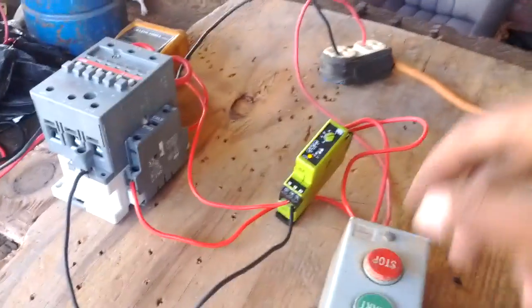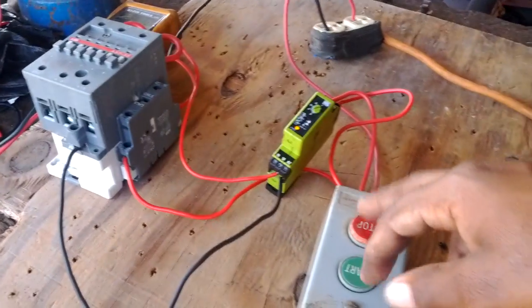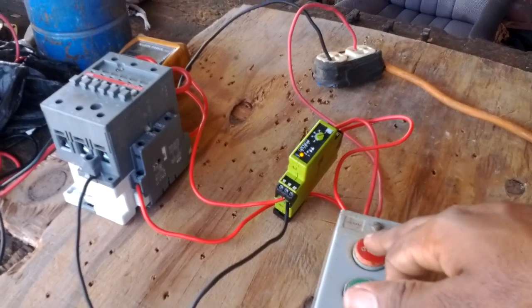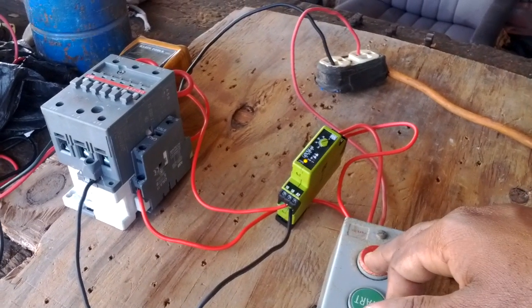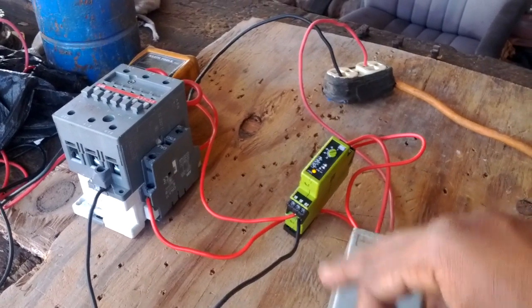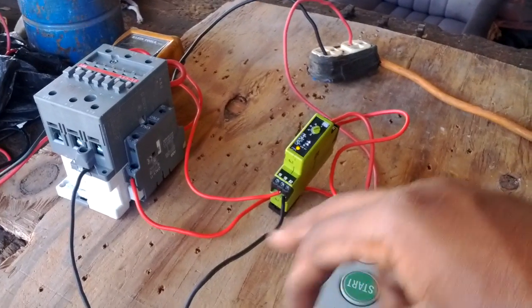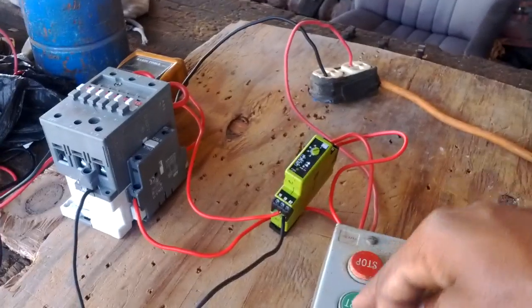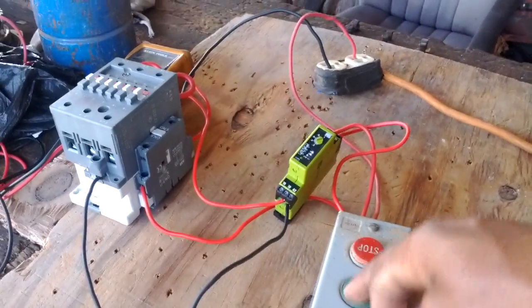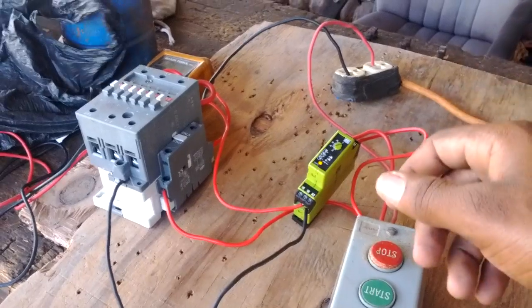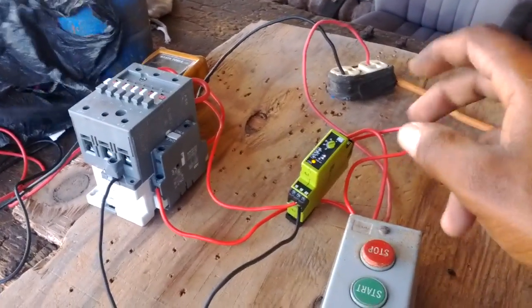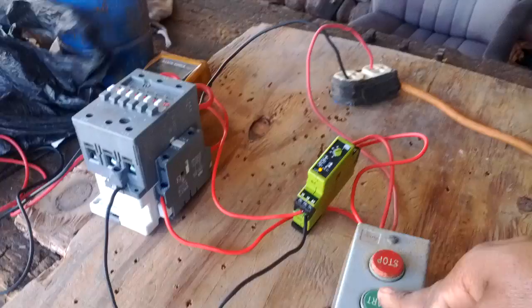If I press the stop button now, the timer should reset itself and everything in the control circuit should reset. I should wait at least 10 seconds before I could turn on and press the start button again. My light is off - I'm pressing the start button and I can't do it. Now my light is back on, indicating it's safe to press start. I can energize my equipment again.